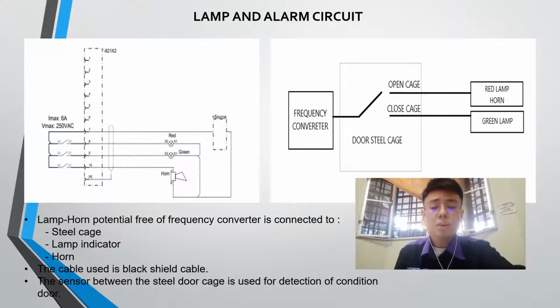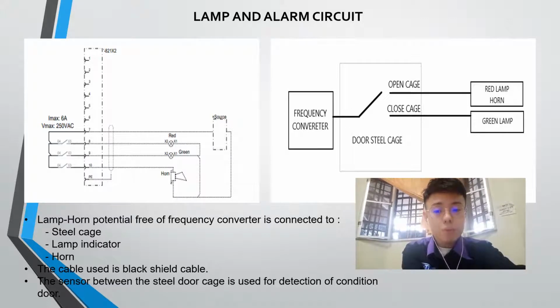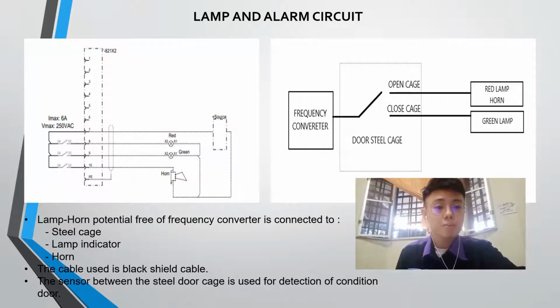The horn is especially used to announce to whoever wants to enter the steel cage that the testing is running. Not only that, it also announces to the one in the control room that the cage is not closed properly and the safety of the testing is not secure. The person in the control room should stop the system and check the condition of the door. Make sure the door is closed and no one is trying to get into the cage. Then the testing can be started again.